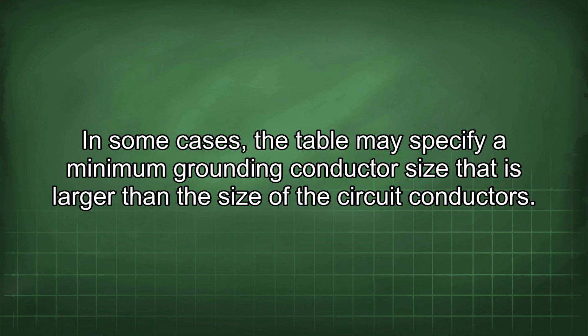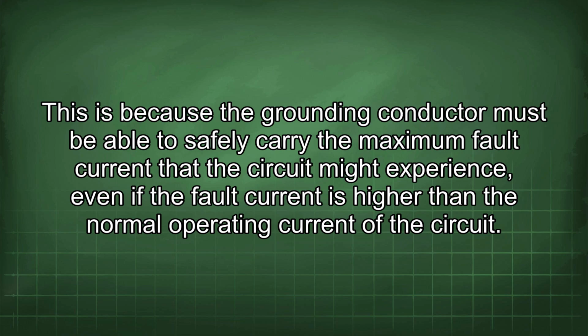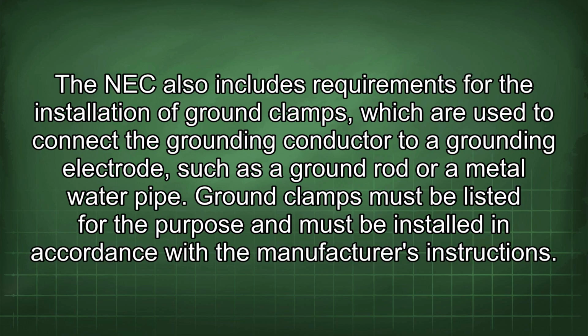In some cases, the table may specify a minimum grounding conductor size that is larger than the size of the circuit conductors. This is because the grounding conductor must be able to safely carry the maximum fault current that the circuit might experience, even if the fault current is higher than the normal operating current of the circuit. The NEC also includes requirements for the installation of ground clamps, which are used to connect the grounding conductor to a grounding electrode, such as a ground rod or a metal water pipe.